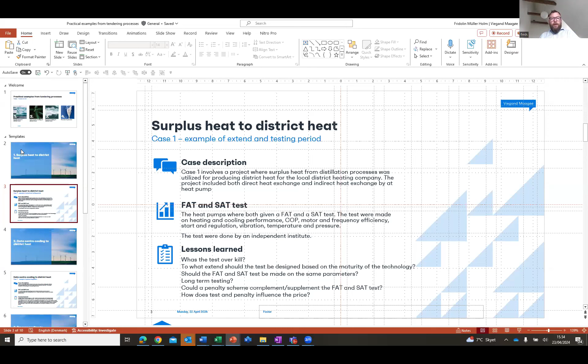This is another example, a data center cooling system where we had a problem with integration. The FAT tests were done at the supplier's facility and were found okay. But during the SAT tests, we discovered design issues that were not taken into account during the initial design of the system — a design problem that appeared during startup.